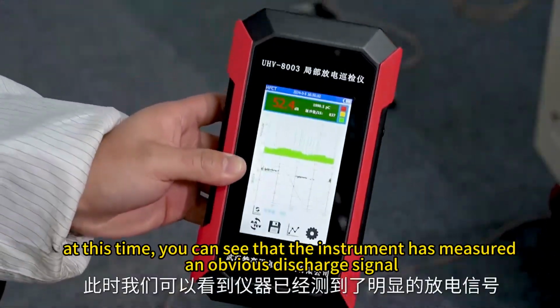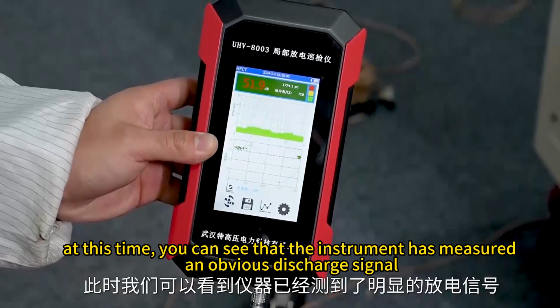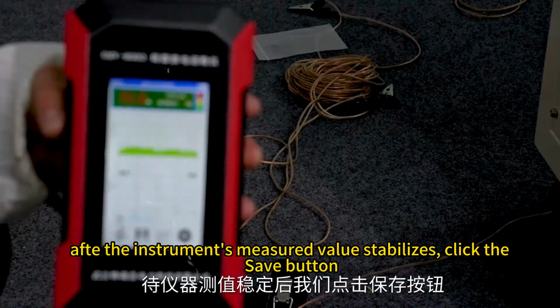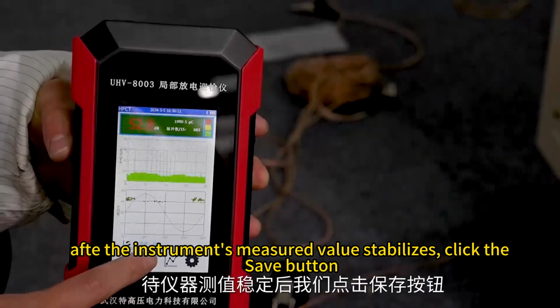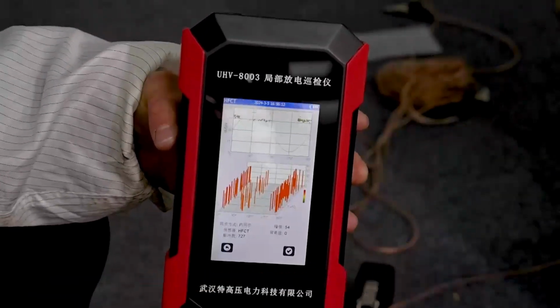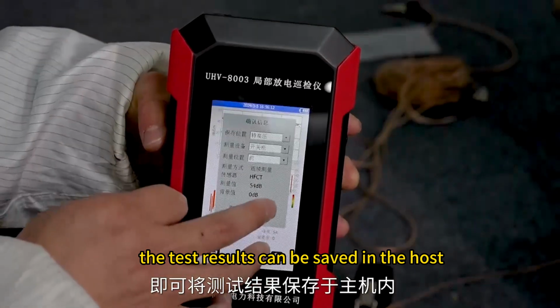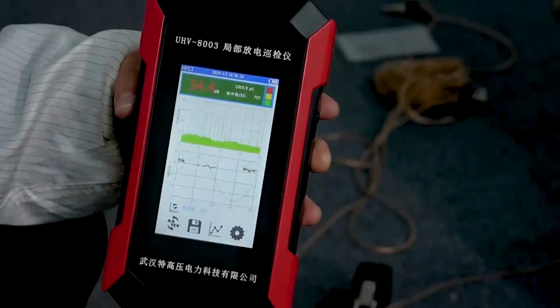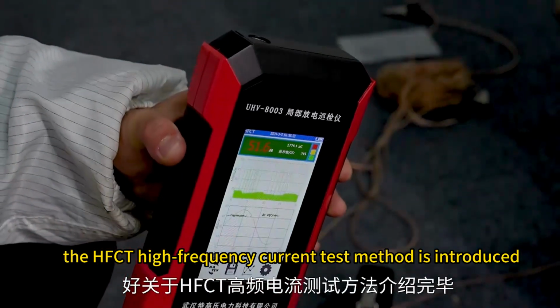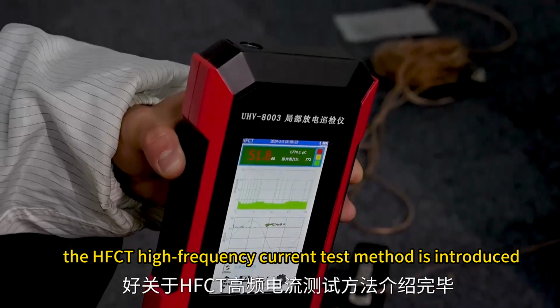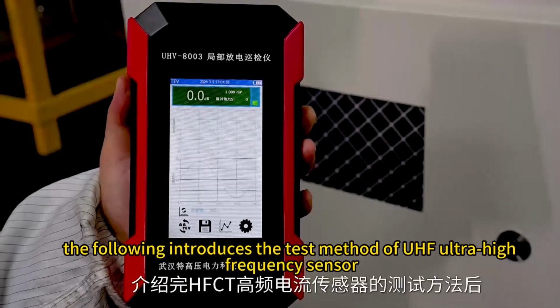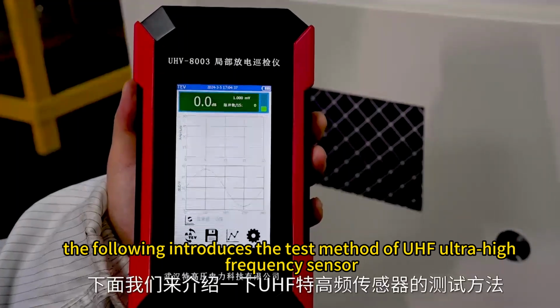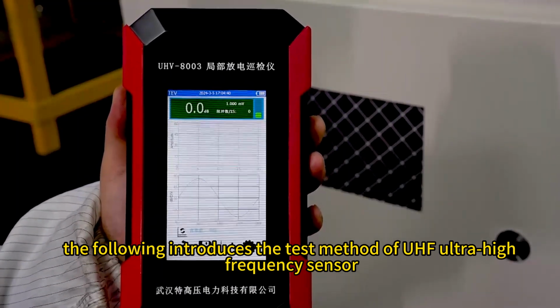At this time, you can see that the instrument has measured an obvious discharge signal. After the instrument's measured value stabilizes, click the Save button. The test results can be saved in the host. The HFCT high-frequency current test method is introduced. The following introduces the test method of UHF ultra-high frequency sensor.